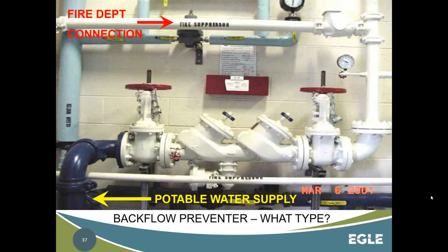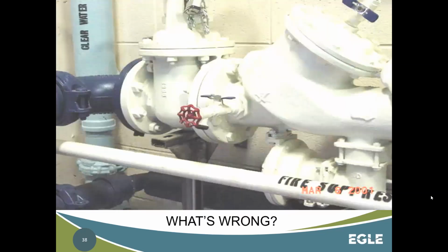But in this case, we've got our potable water supply in the dark blue, the RPZ was installed, and then we have our white plumbing, which is the actual fire suppression going beyond it through the building. So from that picture, though, there was one issue that we found with the RPZ setup, and it's what we've got centered in this picture right here.